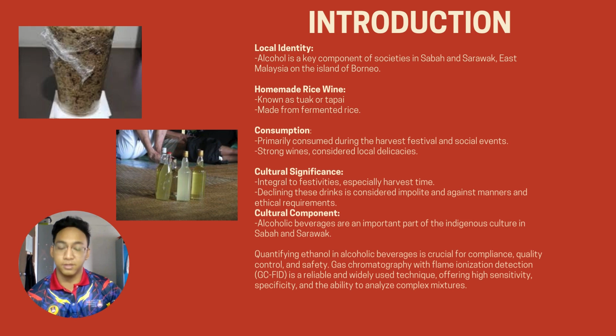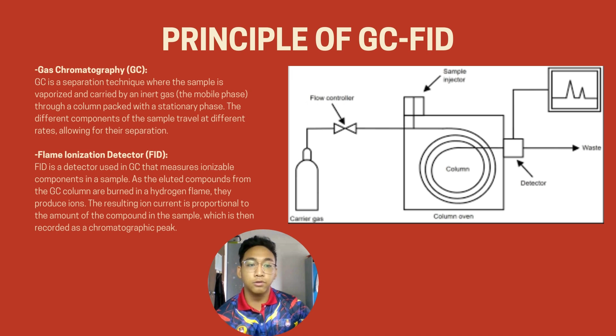Next, Ethan will explain the principle of the GC-FID and more details about the flame ionization detector, which is FID. Gas chromatography is a separation technique where the sample is vaporized and carried by an inert gas, the mobile phase, through a column packed with a stationary phase, allowing the different components of the sample to travel at different rates and separate. The flame ionization detector, FID, is a detector used in GC that measures ionizable components in the sample as the eluted compounds from the GC column are burnt in a hydrogen flame.